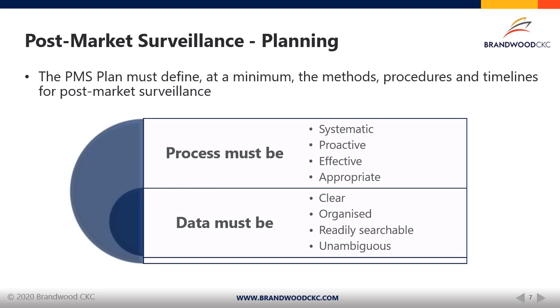And the plan must also give the details on what's going to be required in the post-market surveillance report and the periodic safety update report, which we will discuss later. The final thing it should include is details on the post-market clinical follow-up or a justification for why the post-market clinical follow-up is not applicable for this device.